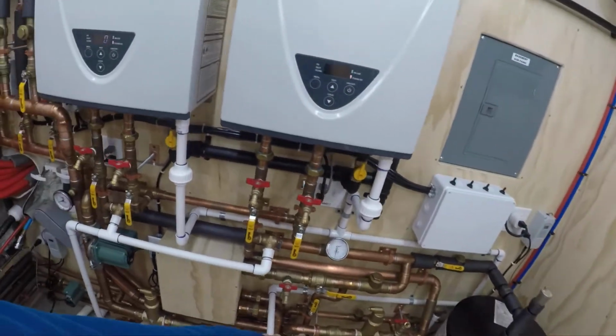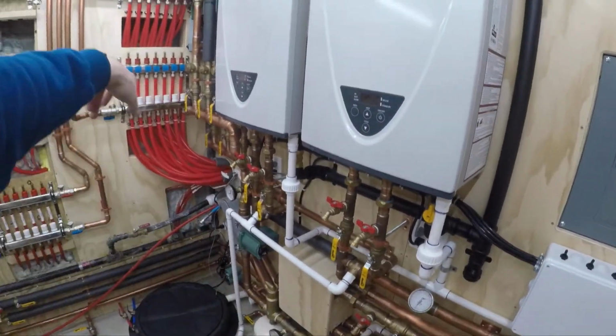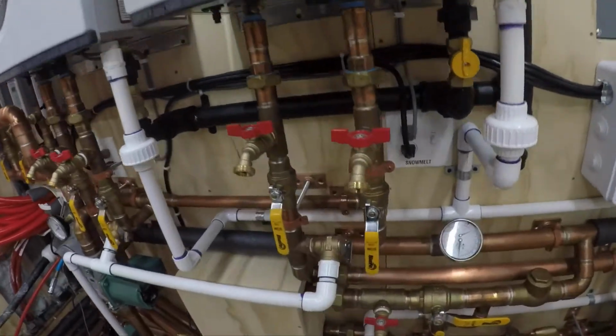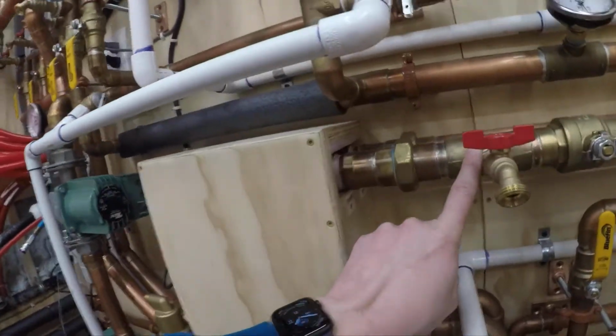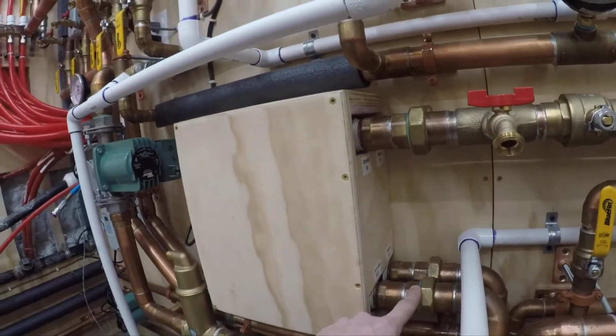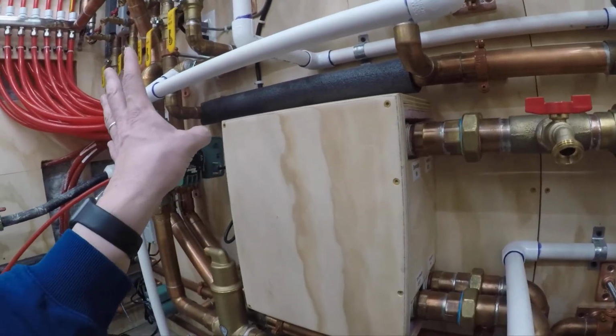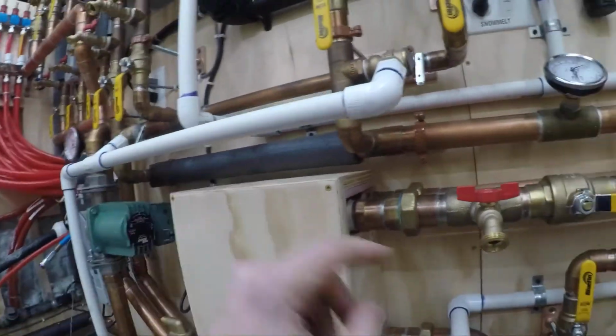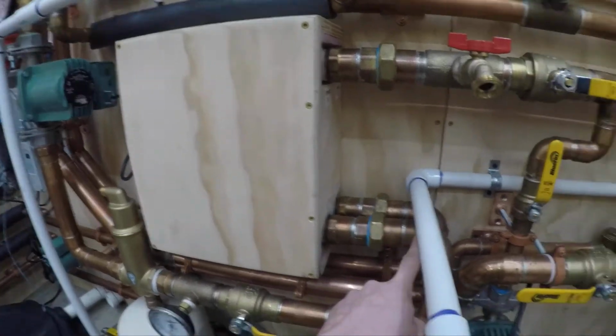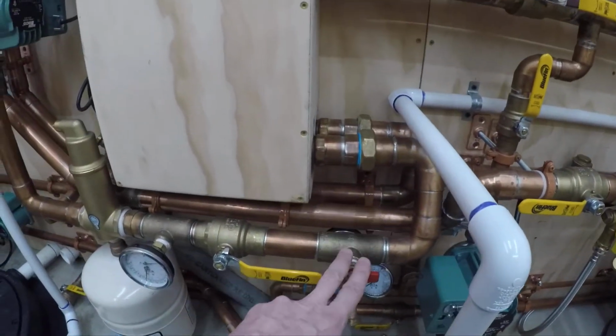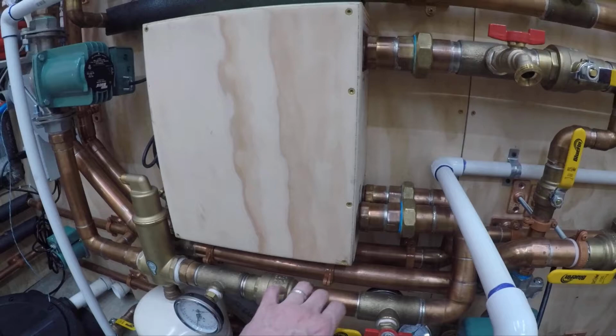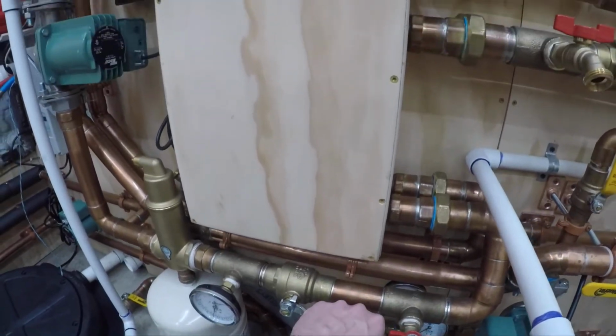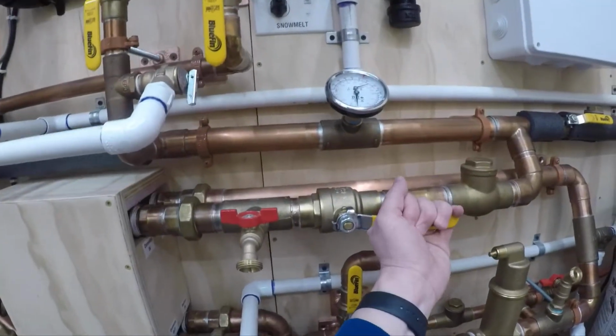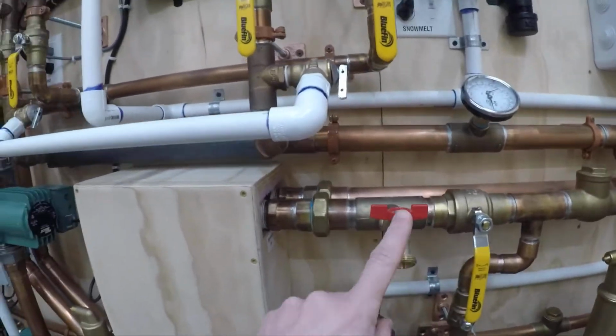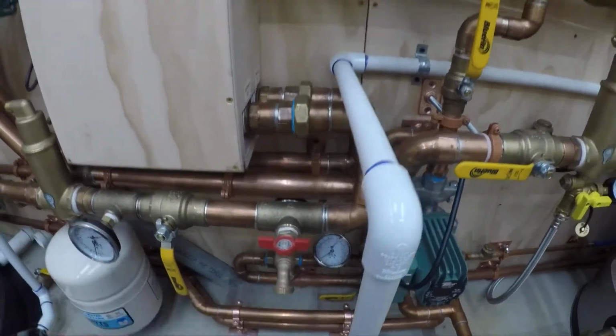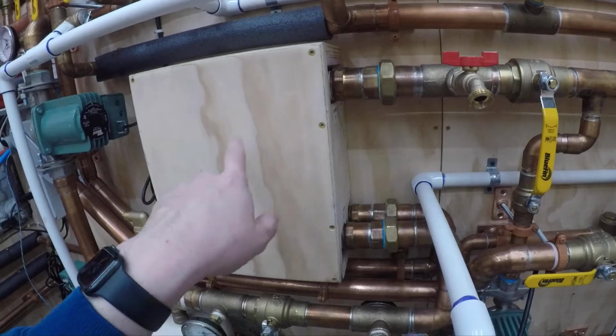I shouldn't say everything, because some of these lines are the primary loop for the heating side. But anyway, hot water comes in here, comes out here. When there's no call for heat, the radiant's off, the snow melt's off, it just travels right through. Okay, comes down around. I have a drain and a shut off, so that I can shut it off here, I can shut it off here, I can hook my hoses up here and here, and I can flush this domestic side of that heat exchanger.